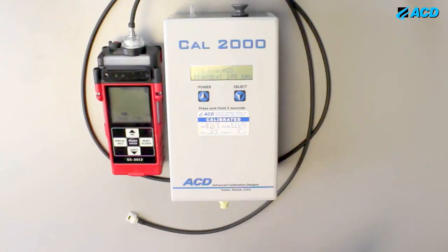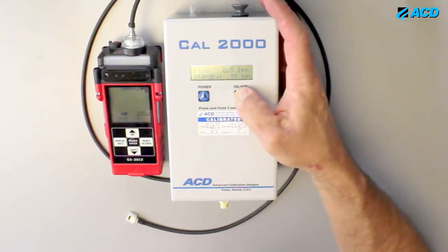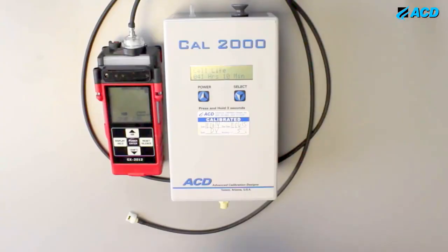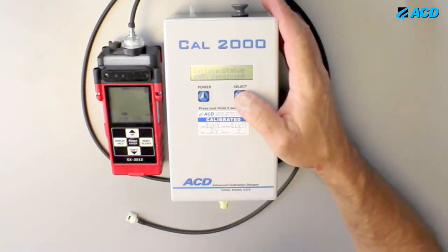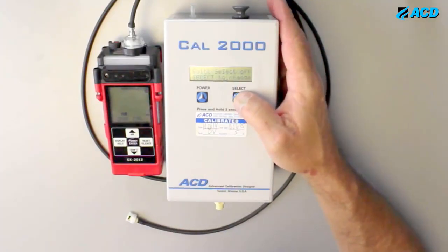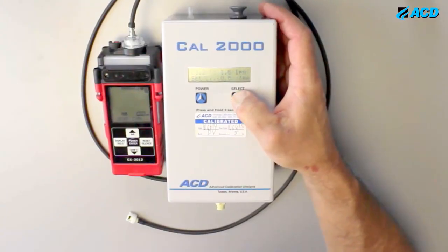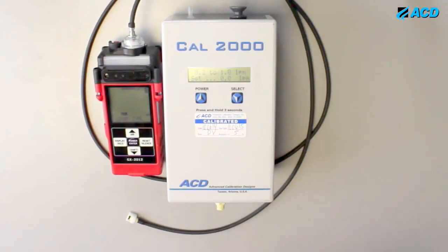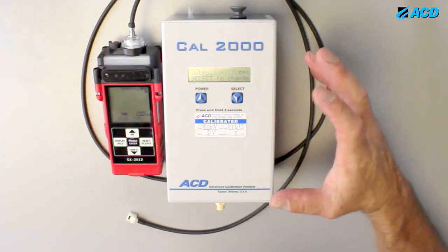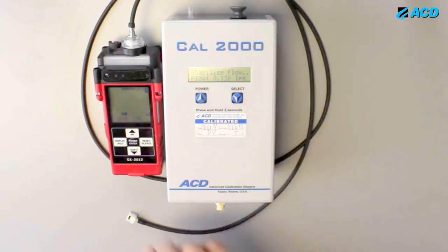But I let go of it, so now we can see that, okay, it's coming back to life. All right. So to avoid a flow failure problem, what I can do is shut the pump off on the Cal 2000, flow 0.5, select to change. I'll set it to 0, right? And then it goes into what we call sample draw mode. So it asks me to stabilize the flow.